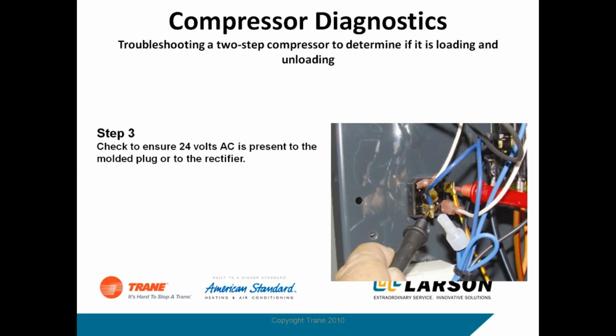So when you're working on a two-stage or two-step compressor, Y1 energizes the contactor to bring the compressor on, and then Y2 energizes this rectifier to energize the solenoid in the head of the compressor. So if you have a problem with the solenoid, say the solenoid shorted out or the rectifier shorted out, what can happen is when you energize Y2, it may blow the fuse on the board on the furnace. And I run into that every now and then, where if the fuse is blowing on the furnace intermittently, start checking out, ohm out your Y2 circuit, see if you have a ground or a short somewhere.